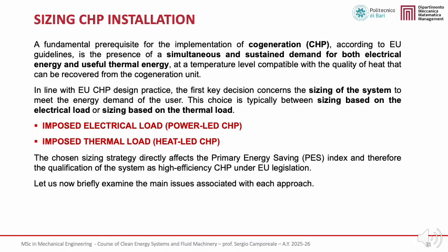In this slide, we introduce the main typologies of CHP installation, following the design framework adopted in European guidelines. A fundamental prerequisite for implementing cogeneration is the presence of a simultaneous and sustained demand for both electrical energy and useful thermal energy at a temperature level compatible with the quality of heat that can be recovered from the CHP unit. Once this condition is satisfied, the first key design decision concerns how the system is sized in order to meet the user's energy demand.